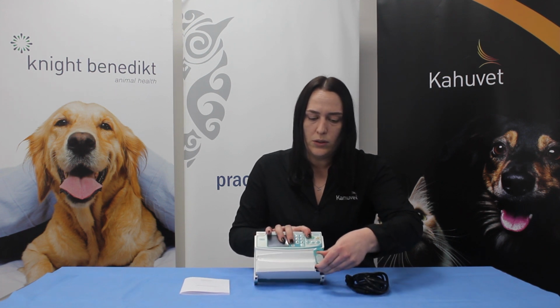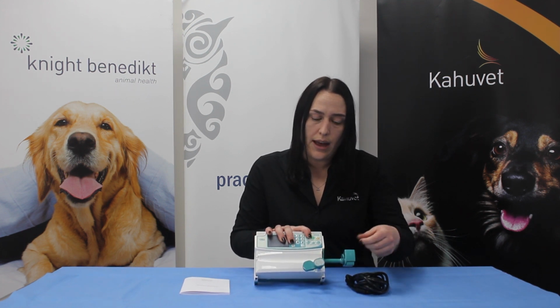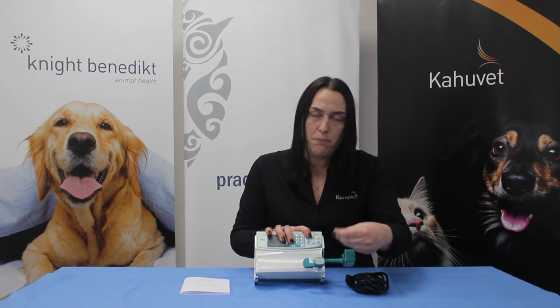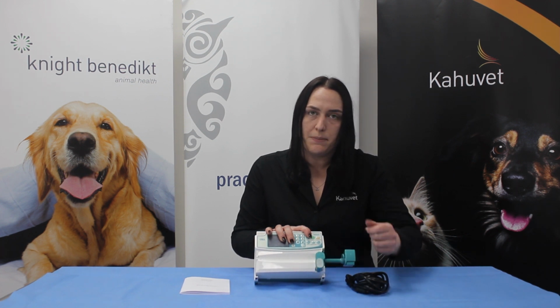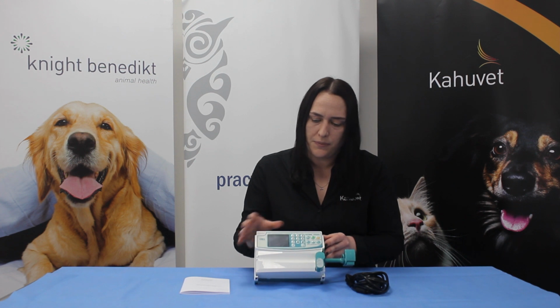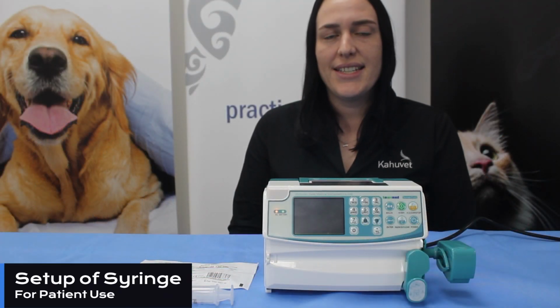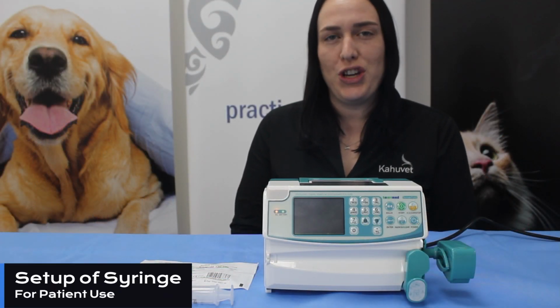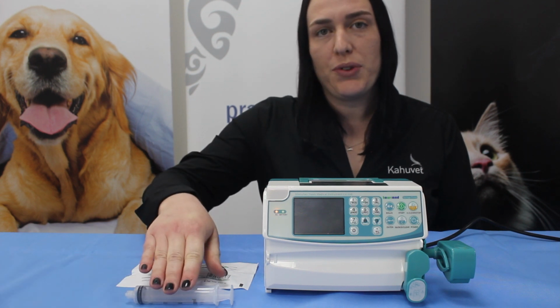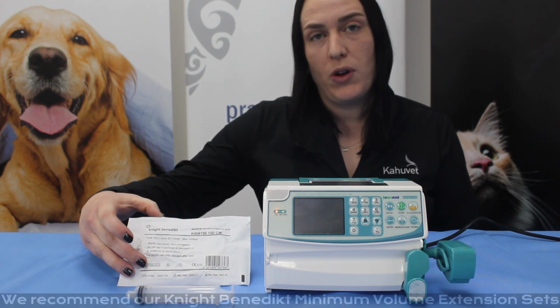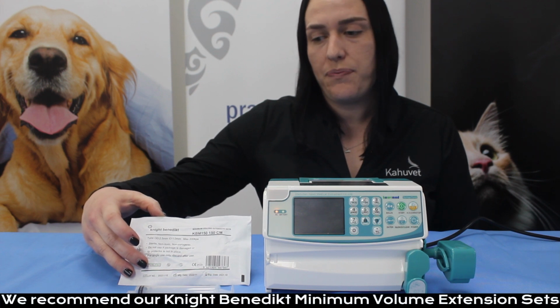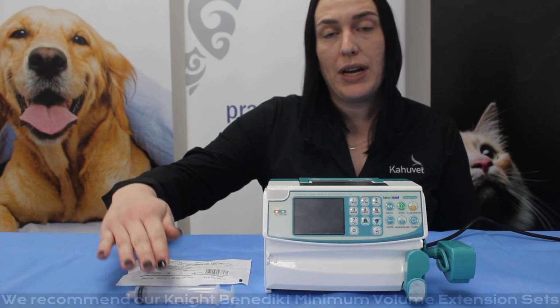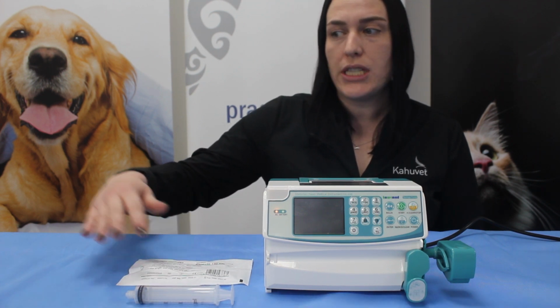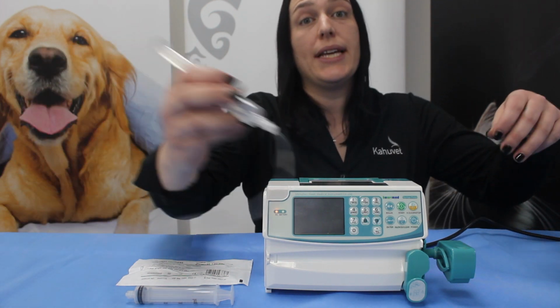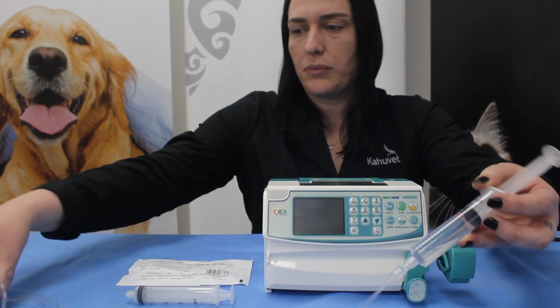We also have the syringe holder, which is a pull and turn clamp. So we can pull and turn, pop our syringe in and just release it back into position to hold the syringe in place. To set up our syringe pump for patient use, we will need a Luer lock syringe and a minimum volume extension set, and once we've filled our syringe and primed our extension set, we'll be able to pop our setup into the syringe pump.